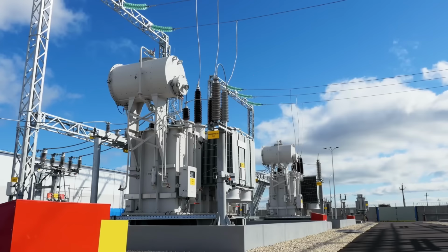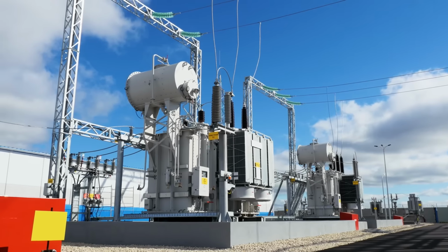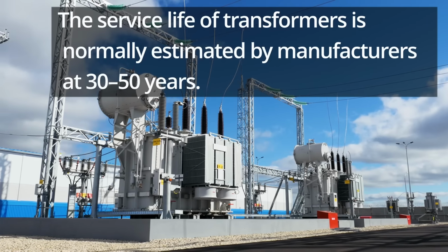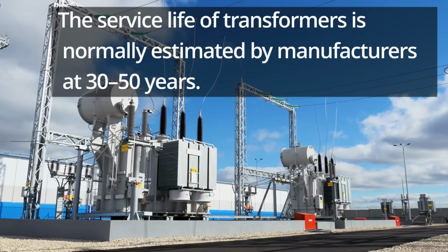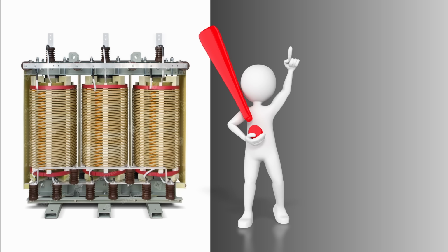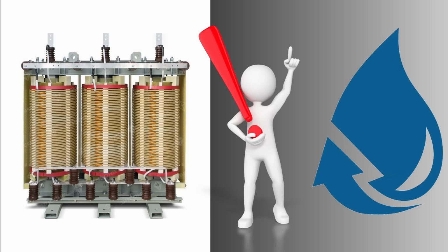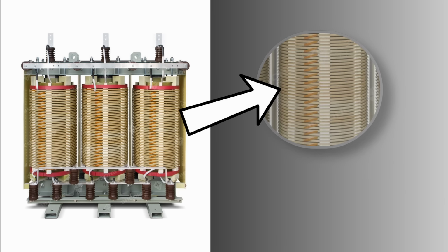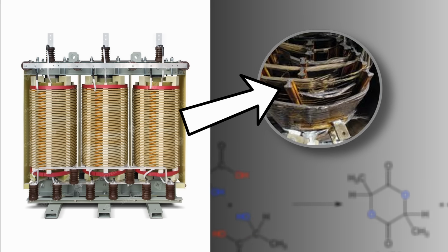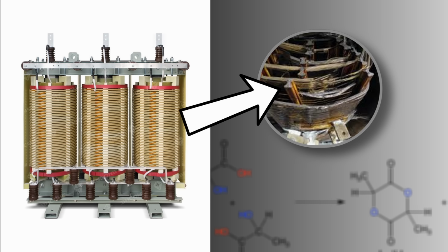The service life of transformers is normally estimated by manufacturers at 30–50 years and basically depends on the insulation condition, which is affected by degradation processes. One of the most serious threats to cellulose insulation is a high water content. It may result in cellulose depolymerization, which deteriorates the mechanical strength of the insulation and makes it more susceptible to degradation due to short circuits, or other stresses.